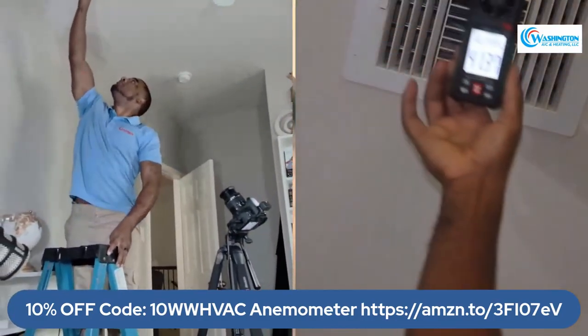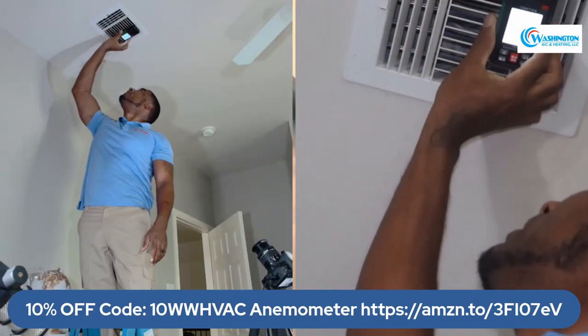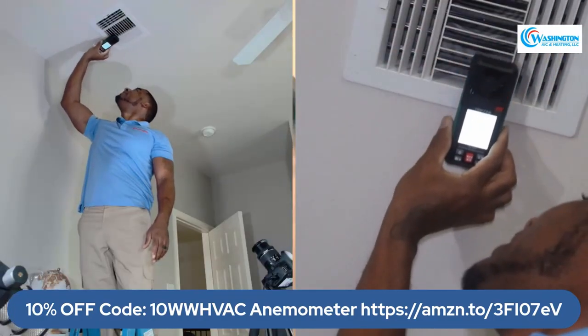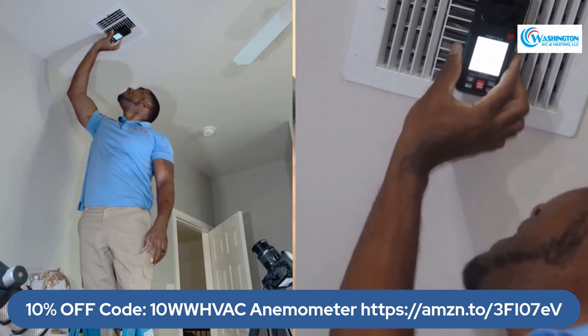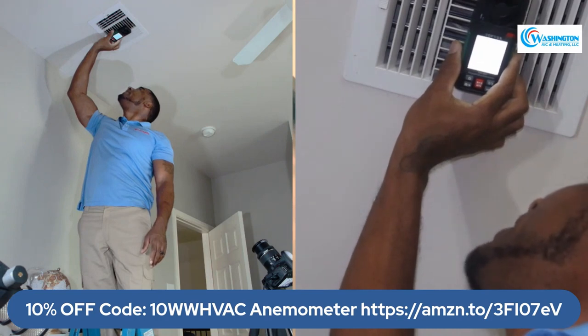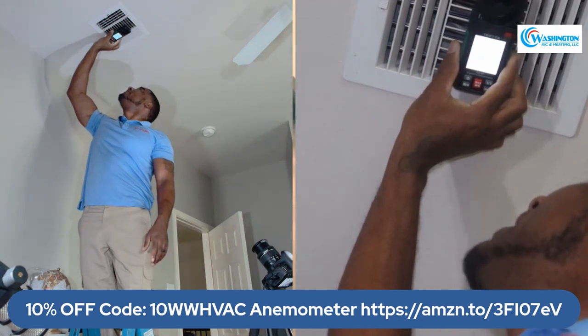All right, as you can see, I'm reading 0. We're gonna go up. It's calculating pretty good. I'm at 573 feet per minute. I got about 57 degrees blowing out.